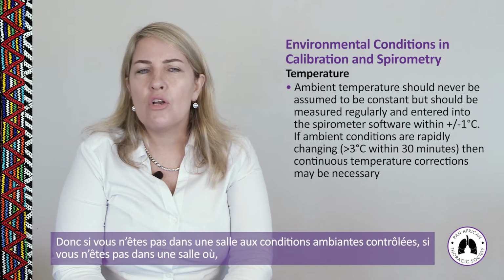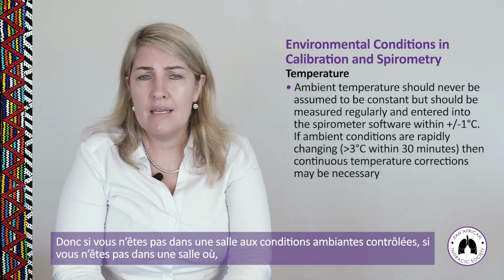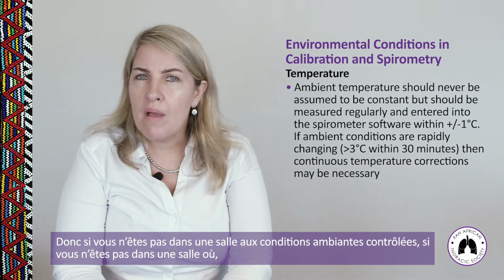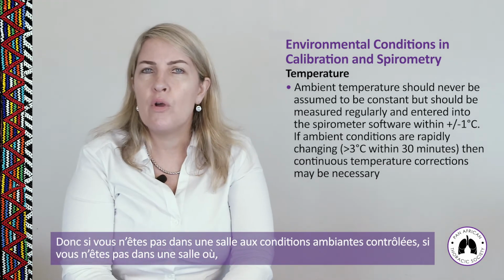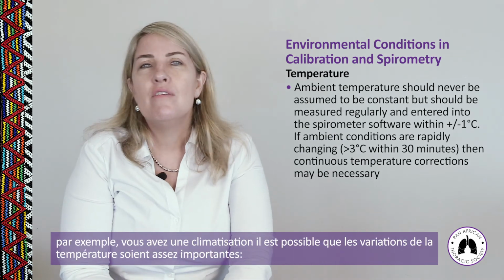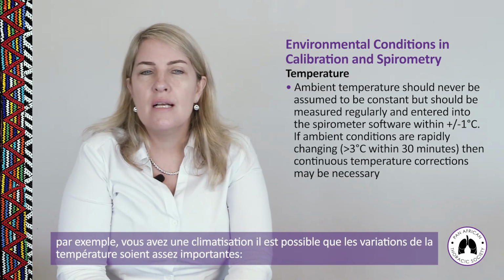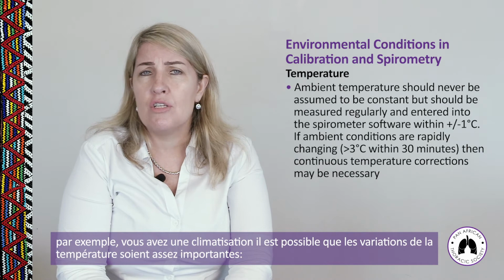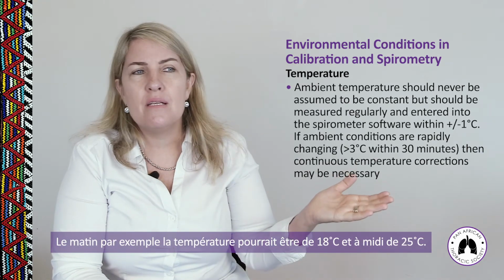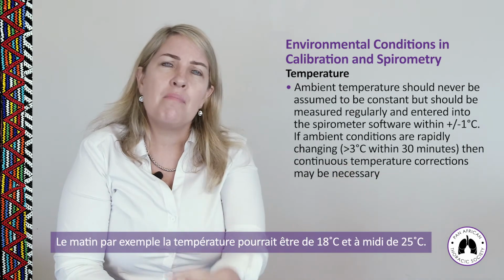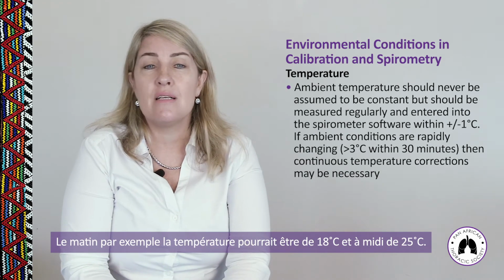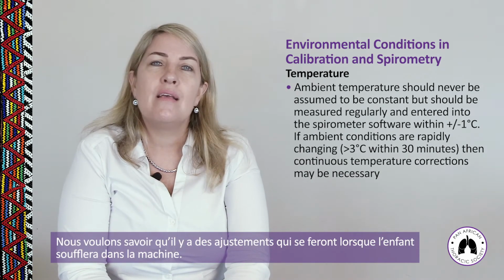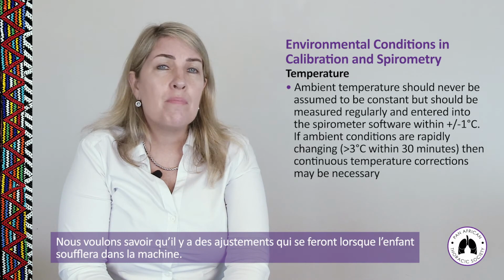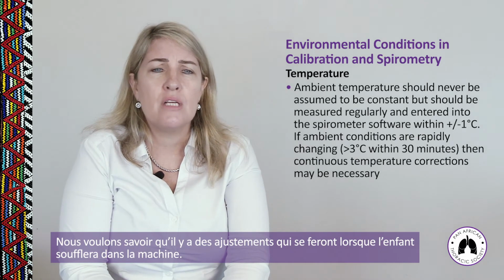So if the ambient conditions are changing rapidly, in other words, if you're not in a weather controlled room, not working in an environment where you have, for example, an air conditioner, you can have big swings in temperature. From the morning, it could be, for example, 18 degrees Celsius, and by lunchtime, it could be 25 degrees Celsius. We want to make sure that there are corrections for that when the patient actually blows onto the machine.